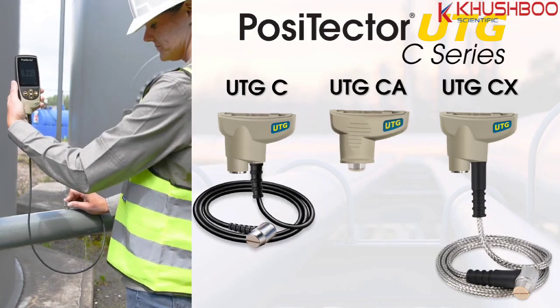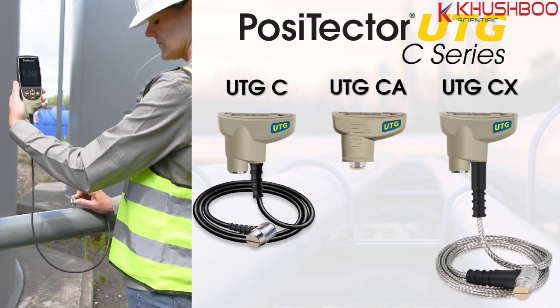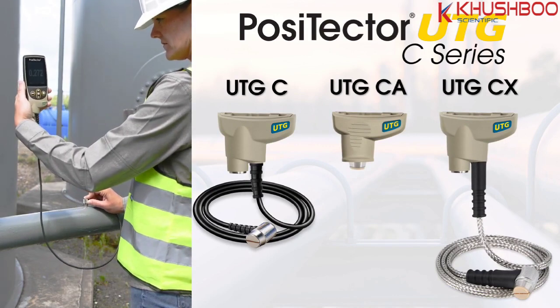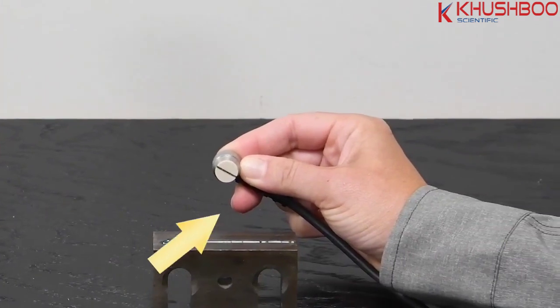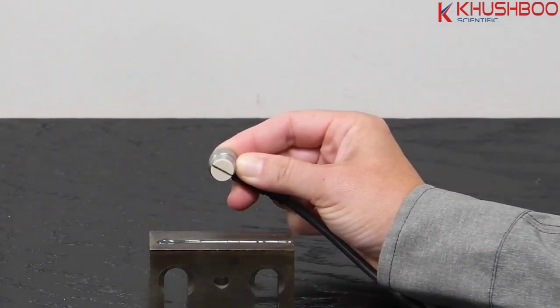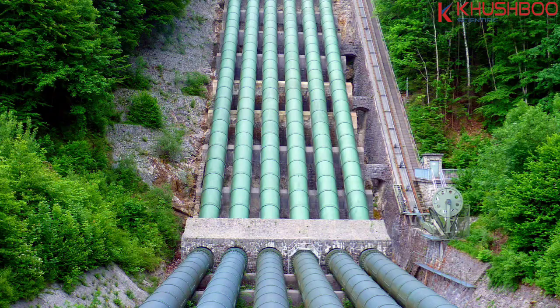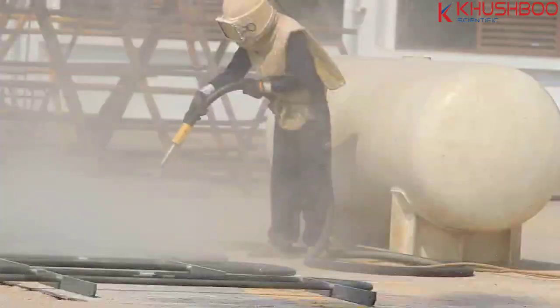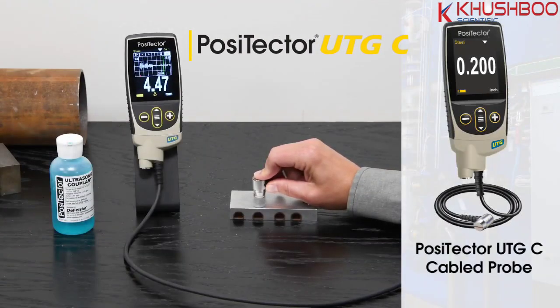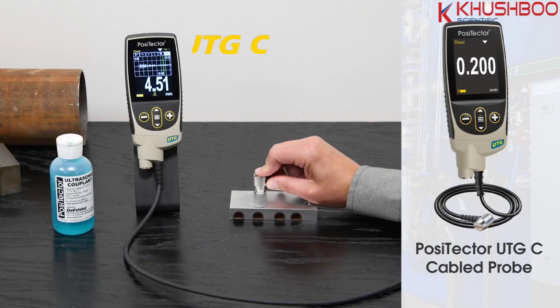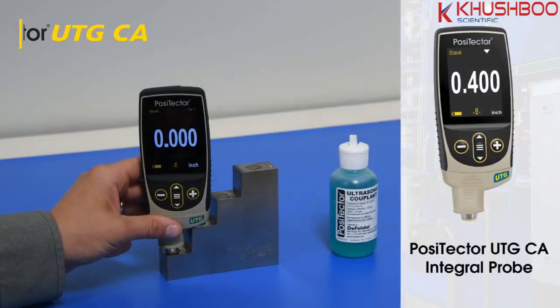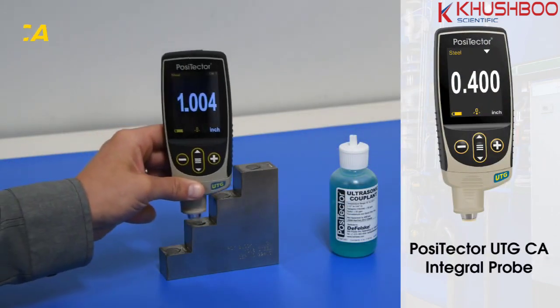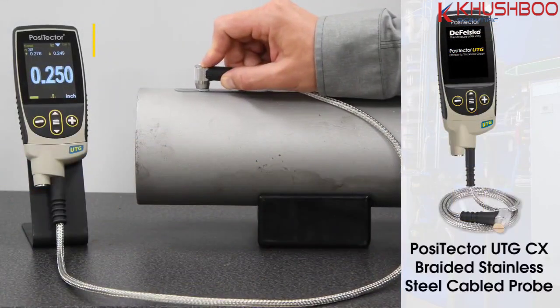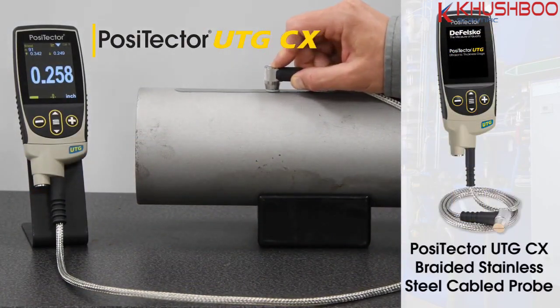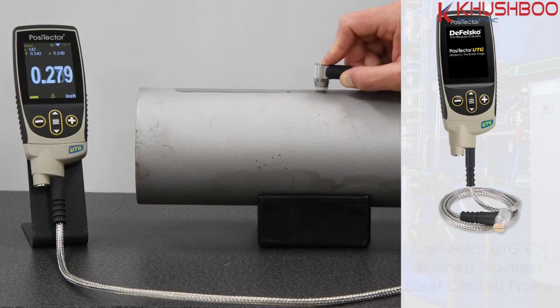The PosiTector UTG-C probe series is ideal for a wide range of applications and features a 5 MHz dual-element transducer. It is ideal for measuring the effects of corrosion on tanks, ships, and other infrastructure. For best accuracy, paint should be removed prior to measurement. Included in this series are the PosiTector UTG-C with a probe on a 1-meter cable, the PosiTector UTG-CA with integral probe ideal for one-handed operation, and the PosiTector UTG-CX with a heavy-duty strain relief and armored cable for demanding applications.